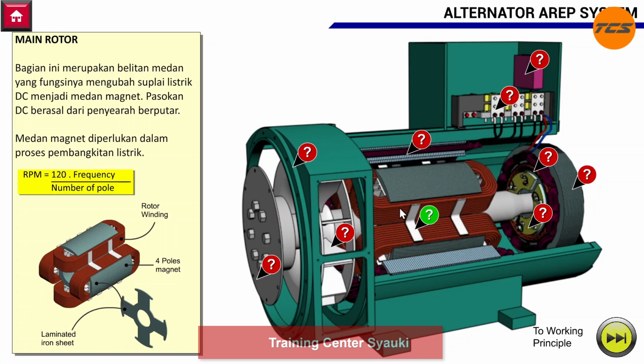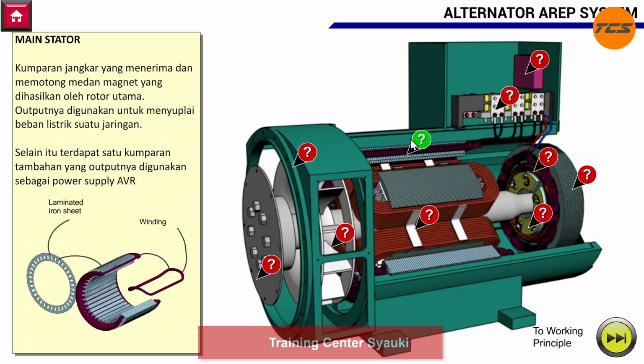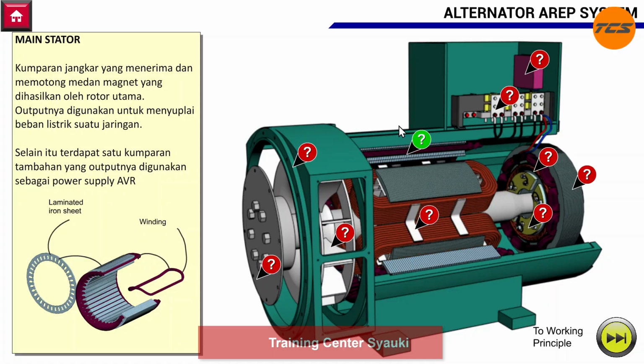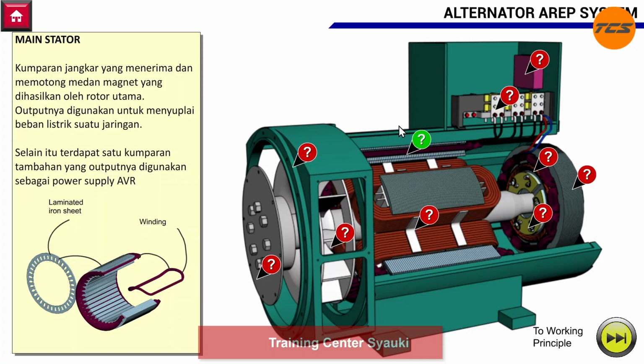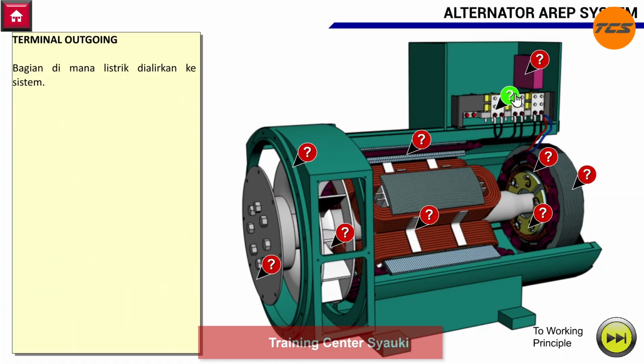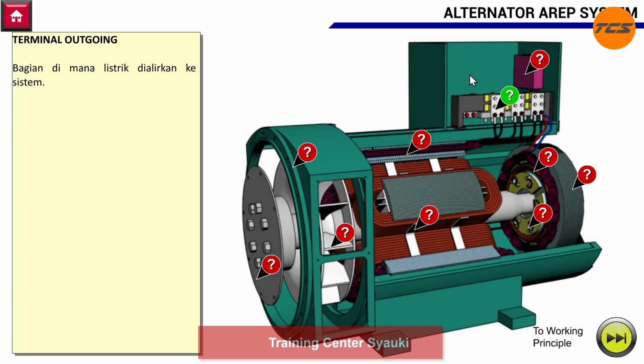The armature winding is located in the main stator. This is where electrical energy is generated. The output of this generator type is 3-phase AC, typically with a maximum voltage of 400 volts. From the main stator, the electrical output is routed to the output terminal, which supplies power to the external electrical system or load.